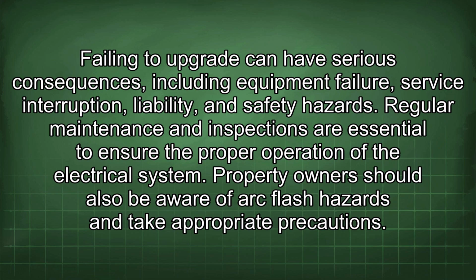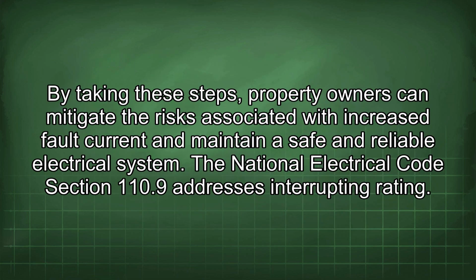Regular maintenance and inspections are essential to ensure the proper operation of the electrical system. Property owners should also be aware of arc flash hazards and take appropriate precautions. By taking these steps, property owners can mitigate the risks associated with increased fault current and maintain a safe and reliable electrical system. The National Electrical Code Section 110.9 addresses interrupting rating.